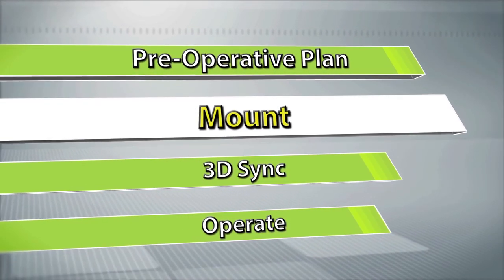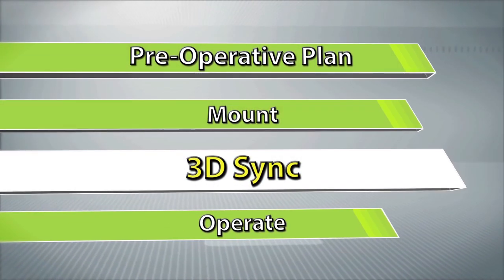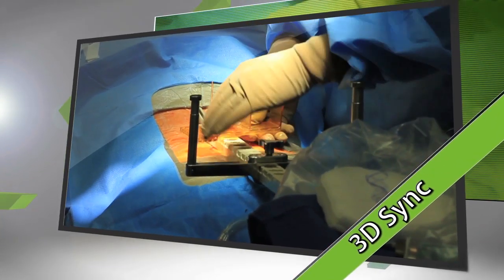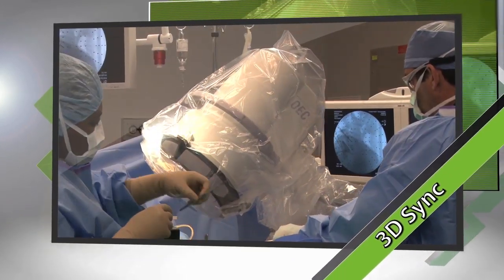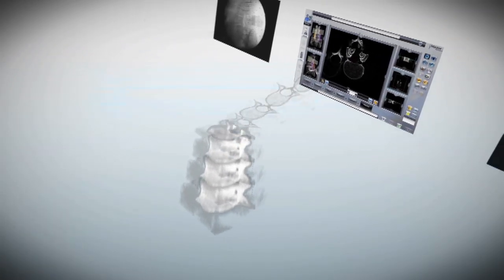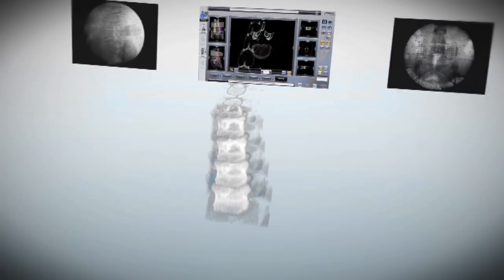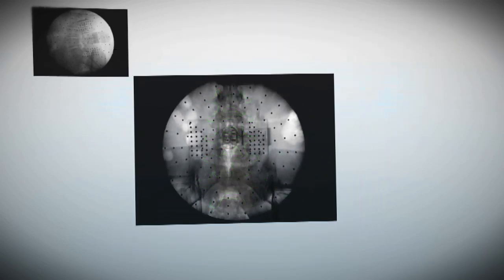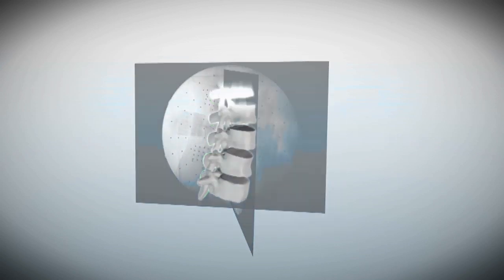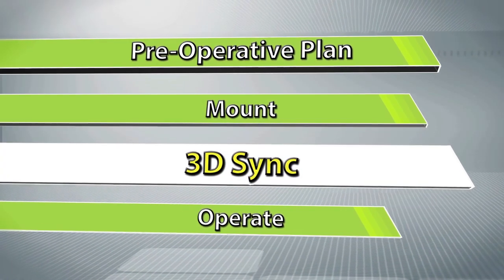Once the mounting platform is in place, matching of the intraoperative anatomy to the preoperative blueprint can be achieved. A 3D marker is attached to the mount, and two fluoroscopic images are taken — an AP and an oblique. Renaissance then matches these intraoperative images to their corresponding location on the preoperative CT, independently registering each vertebra regardless of changes in intervertebral space.